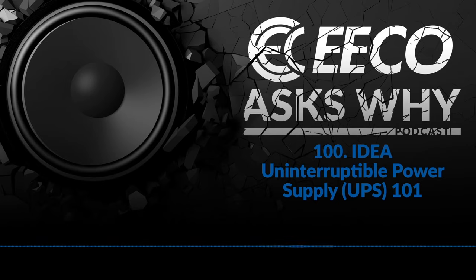Yeah, sure. So the offline UPS is going to be a device that, when you've got good mains voltage—say 120 volts in your wall, for example, if you're backing up some computer equipment—as long as that voltage is within tolerance, it's just going to pass that voltage straight through the UPS out to your devices. It's going to offer some surge protection, and that's about it. Those offline UPSs are typically a little bit less expensive.